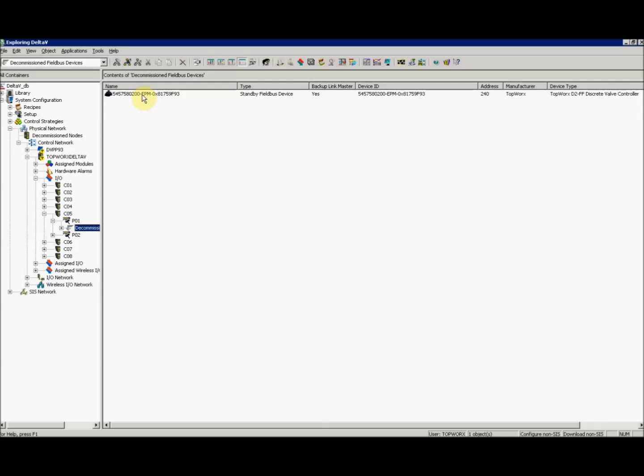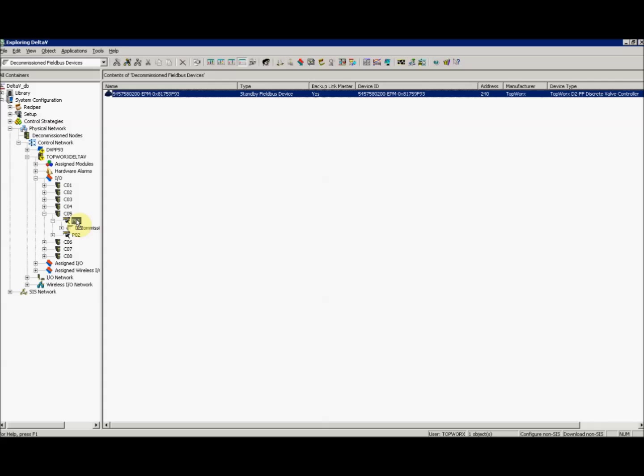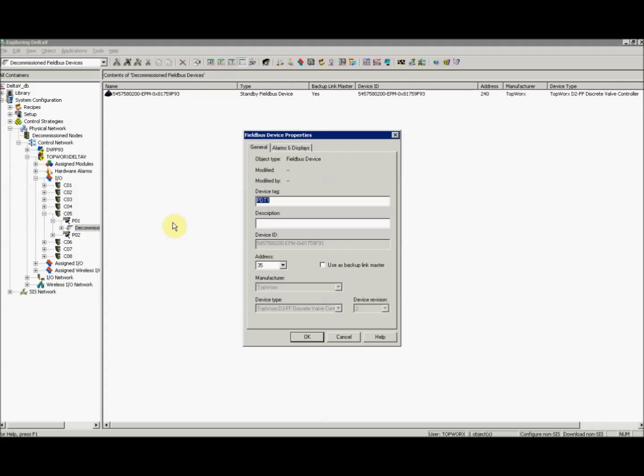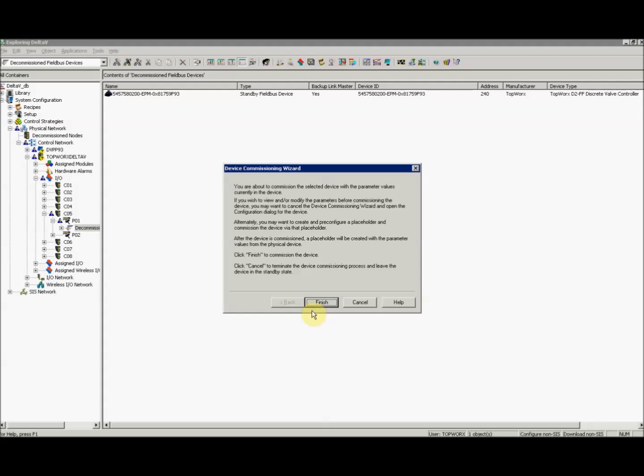Once in standby, you can drag and drop the device to your port, in this case port 1. A tag properties window will pop up. Change what you see fit and go ahead and select OK. A wizard window pops up letting you know that if you have a placeholder set up, you can go ahead and commission this in that placeholder just by dragging and dropping to that pre-configured placeholder, or you can do what we're doing and start a whole new device with a new placeholder by just dragging and dropping to the port. So we'll go ahead and select Finish.